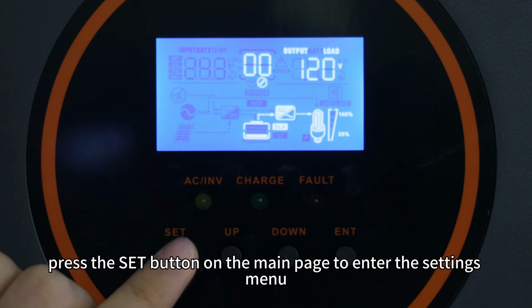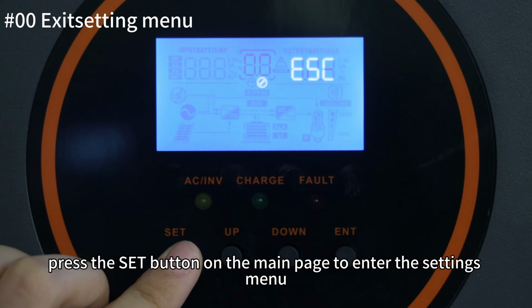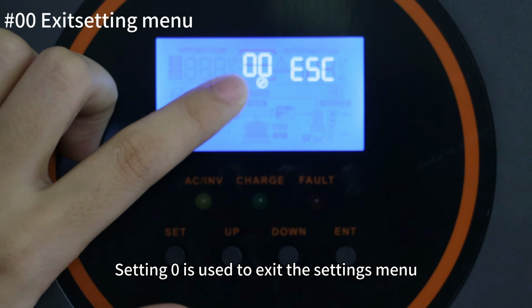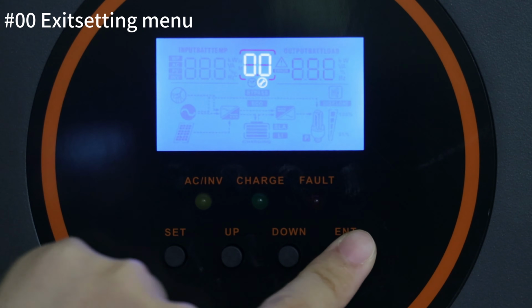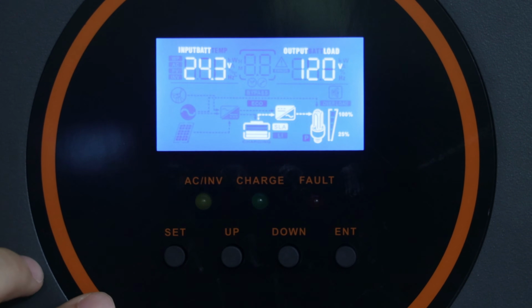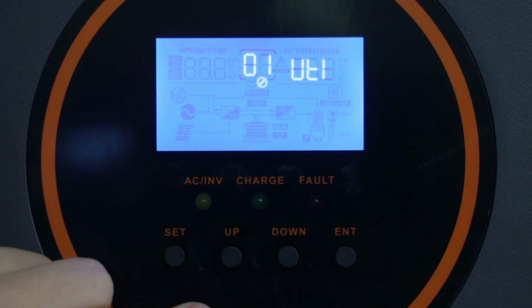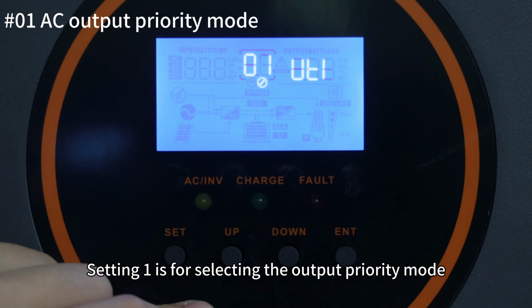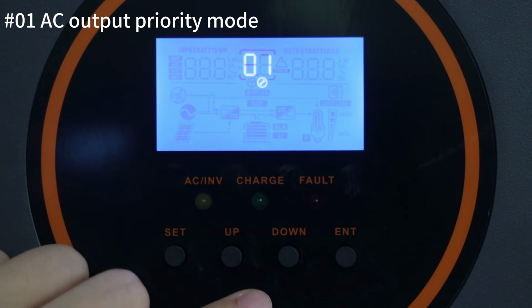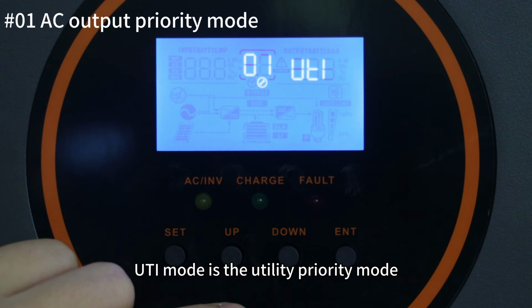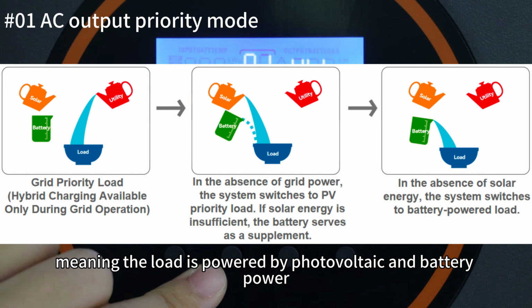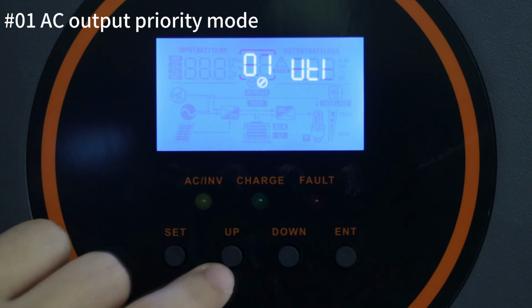First, press the Set button on the main page to enter the settings menu. Setting 0 is used to exit the setting menu. Setting 1 is for selecting the output priority mode. UTI mode is the utility priority mode, where the inverter switches to inverter mode only when utility power is unavailable, meaning the load is powered by photovoltaic and battery power.